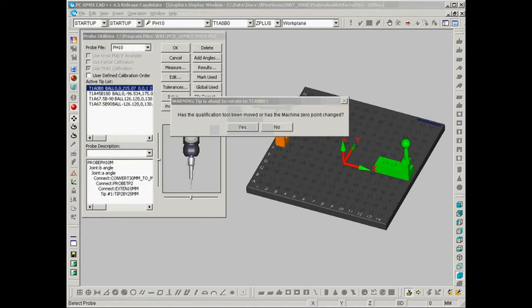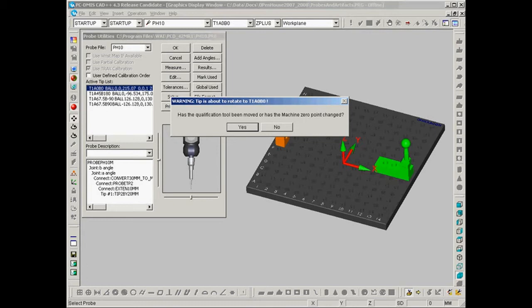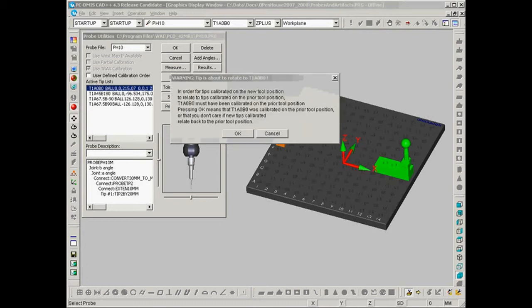Now at the dialog that appears, has the qualification tool been moved or the CMM zero point changed? You want to select yes to this. The next dialog to appear is this long message right here. For now we'll OK past this. We'll discuss this message in just a moment.